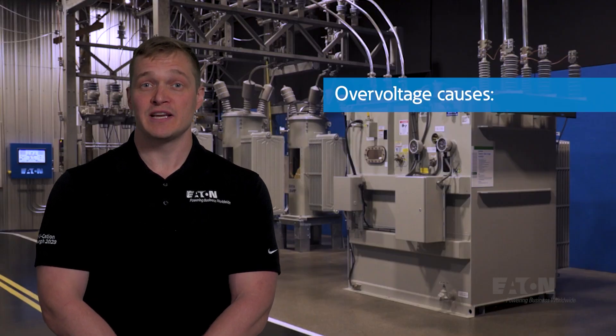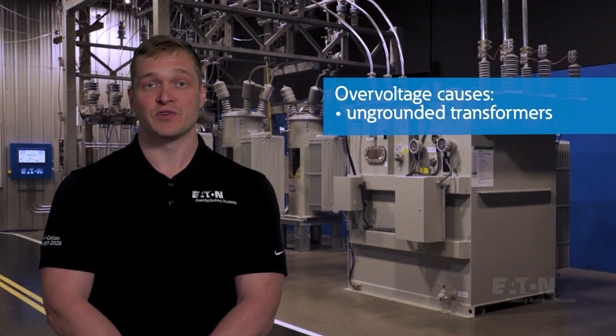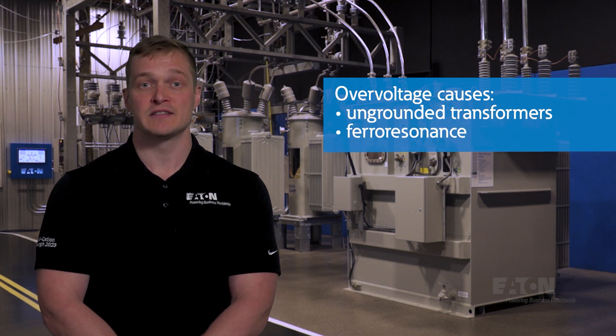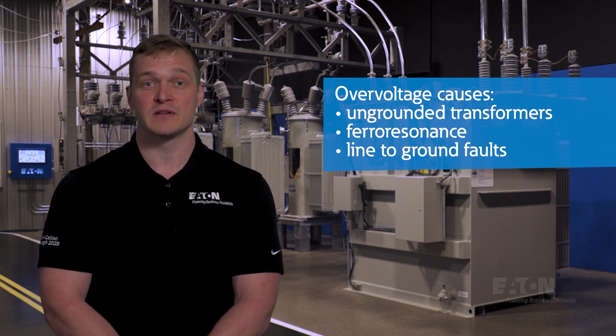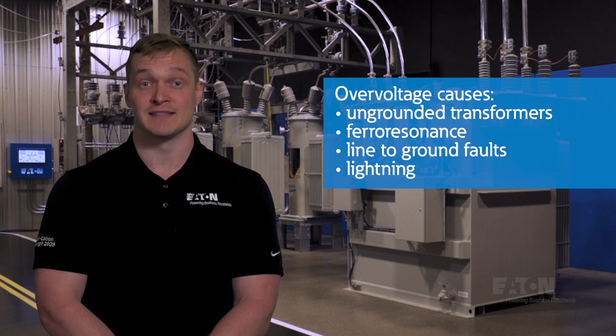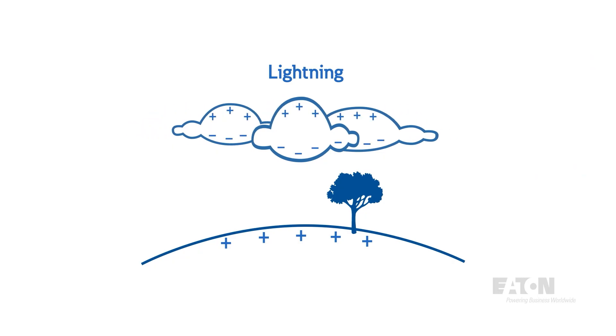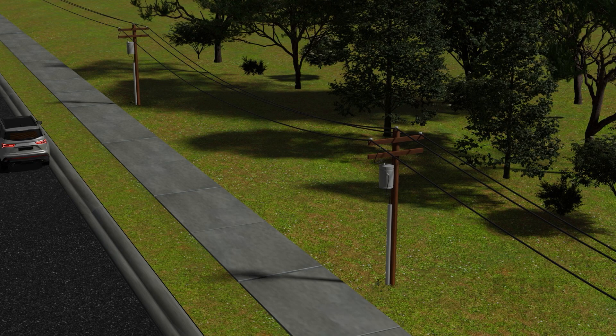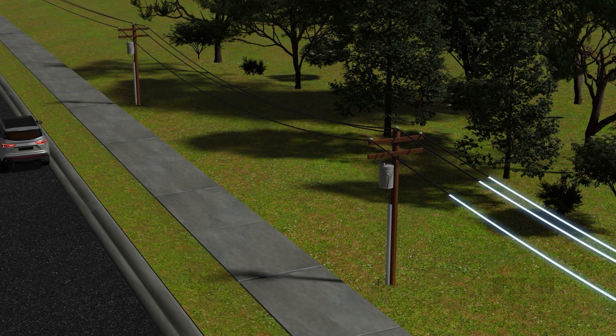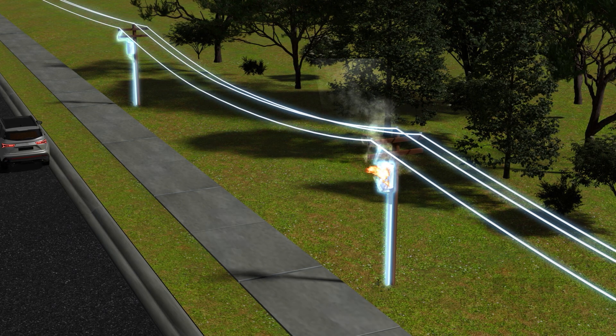While overvoltages may have many causes such as ungrounded transformers, ferroresonance, or line-to-ground faults, by far the most common is lightning. Lightning forms from charge buildup in the clouds. If enough charge builds up, it can overcome the air gap between the cloud and earth and strike in the form of lightning. Electrically, these strikes act as a current source that transfers the buildup charge, inducing an overvoltage that propagates outward from the point of contact.